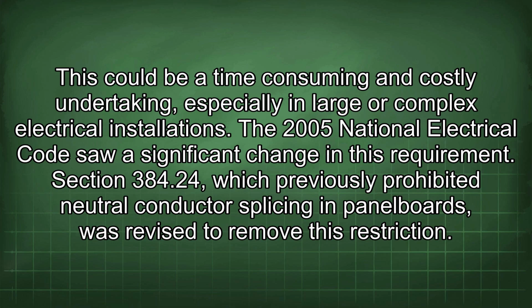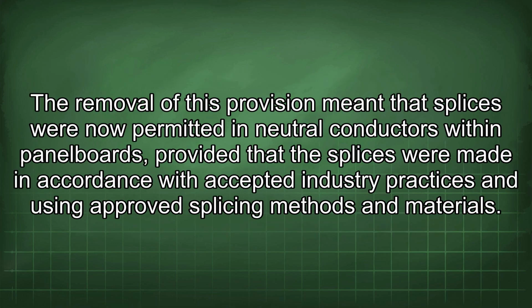The 2005 National Electrical Code saw a significant change in this requirement. Section 384.24, which previously prohibited neutral conductor splicing in panelboards, was revised to remove this restriction. The removal of this provision meant that splices were now permitted in neutral conductors within panelboards, provided that the splices were made in accordance with accepted industry practices and using approved splicing methods and materials.